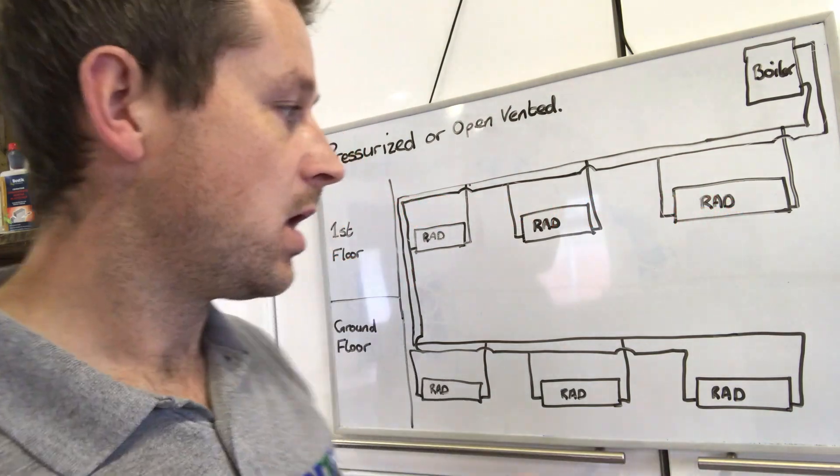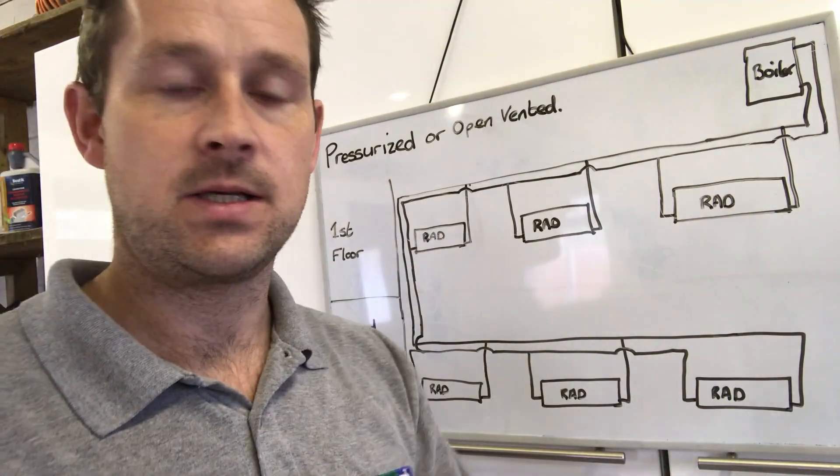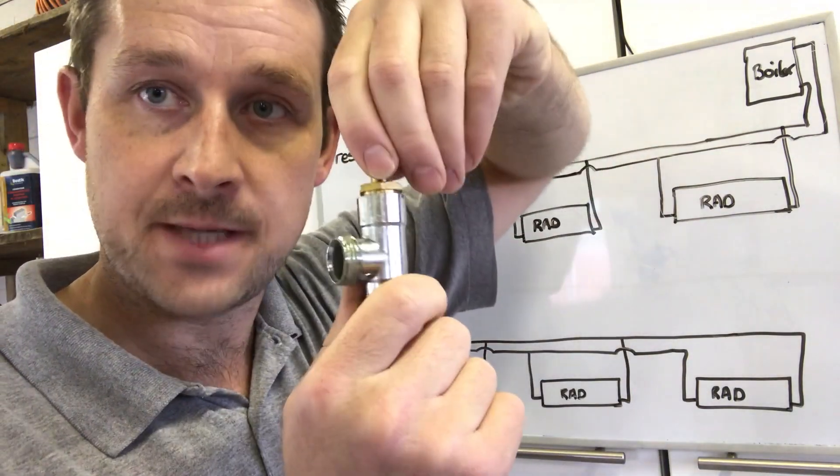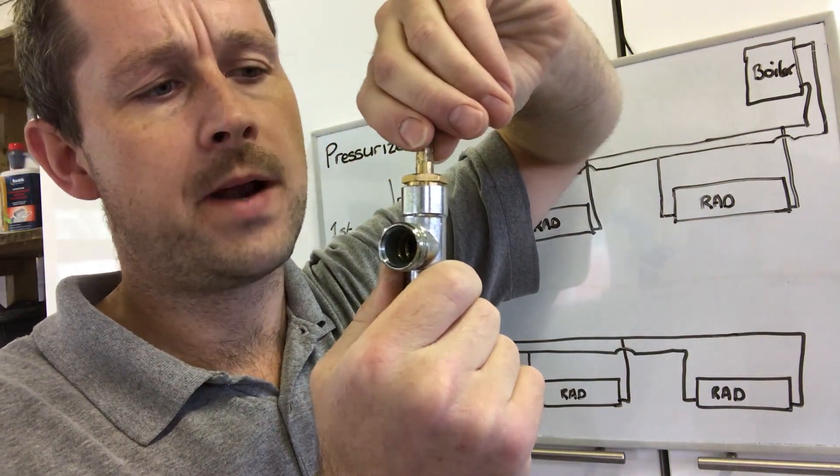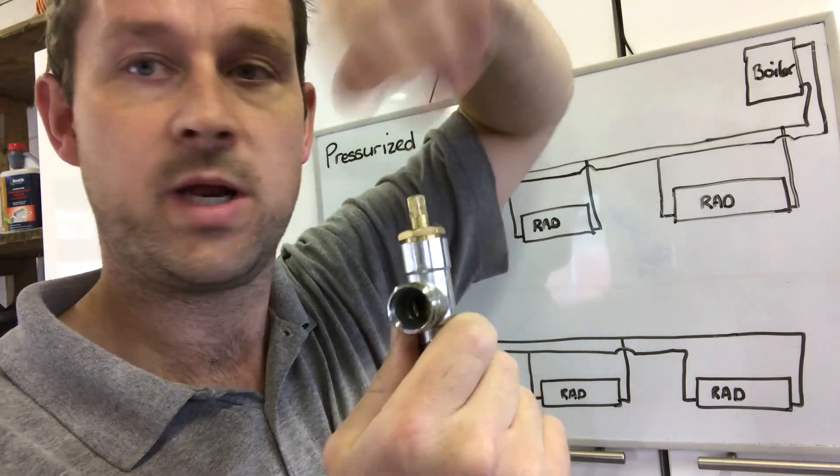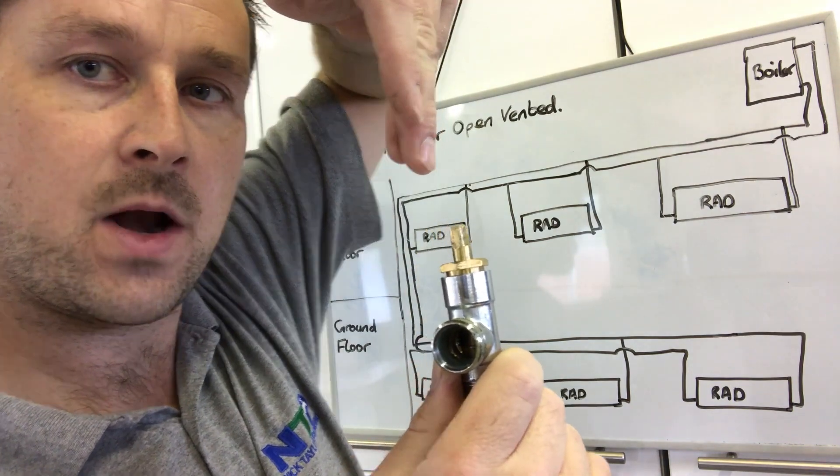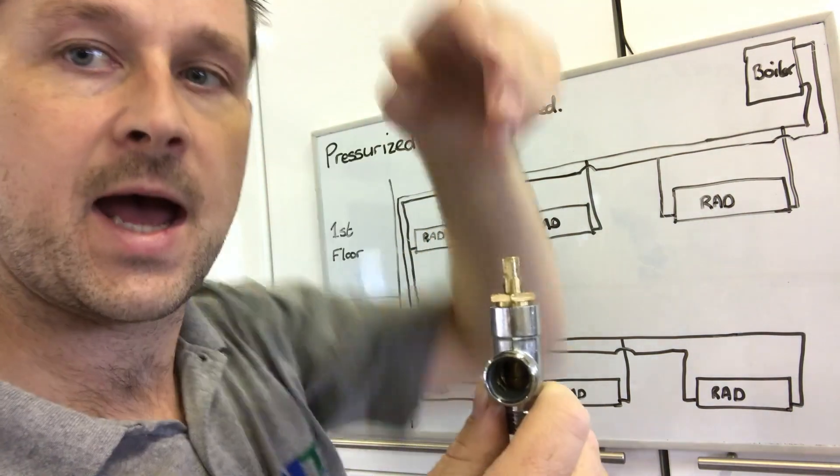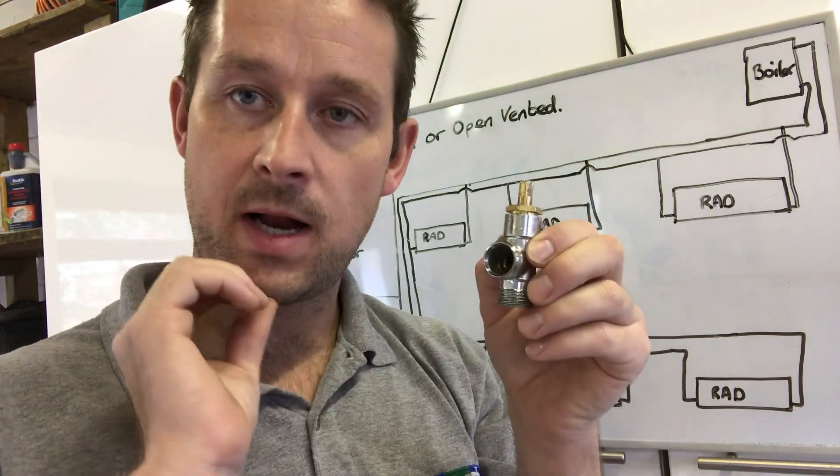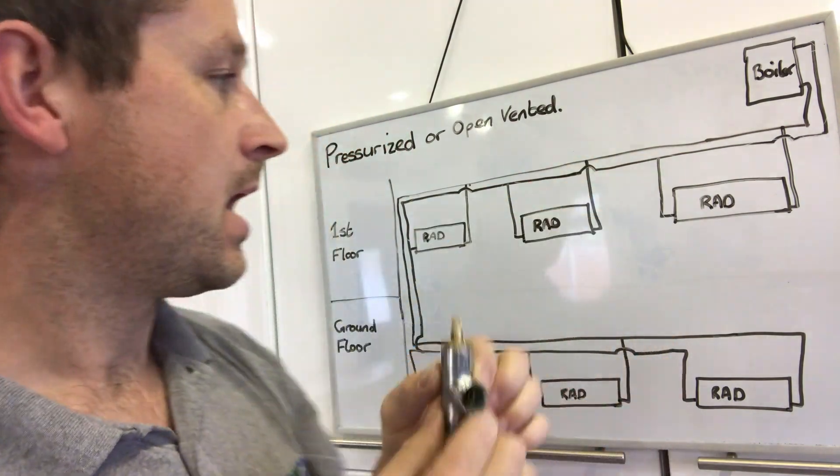Completely close it and then open it one whole turn. So when you get your spanner on it, you've got half a turn and then obviously turn it again another half. What that will do is let a trickle of water through.